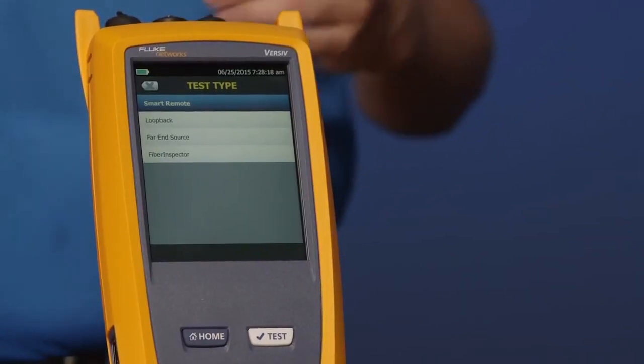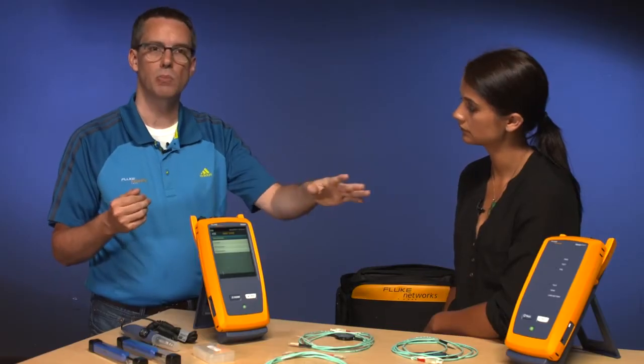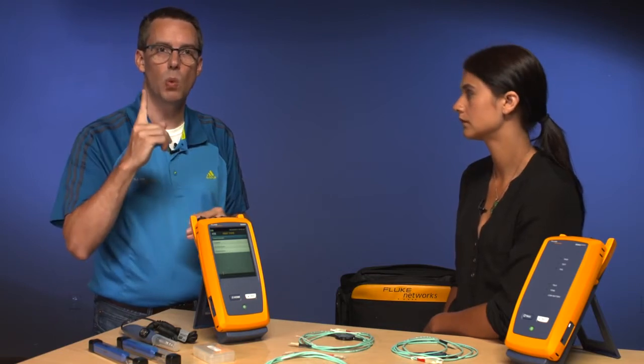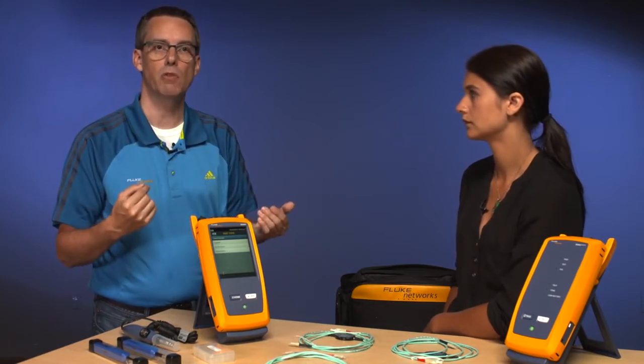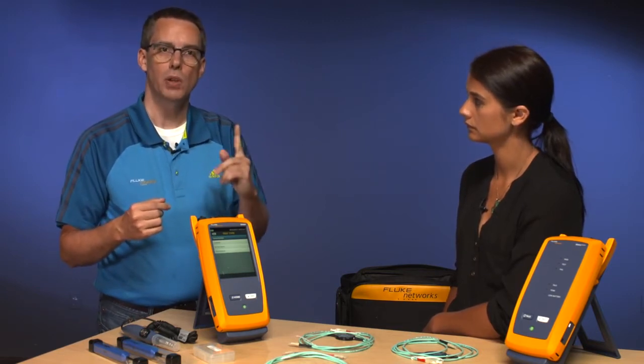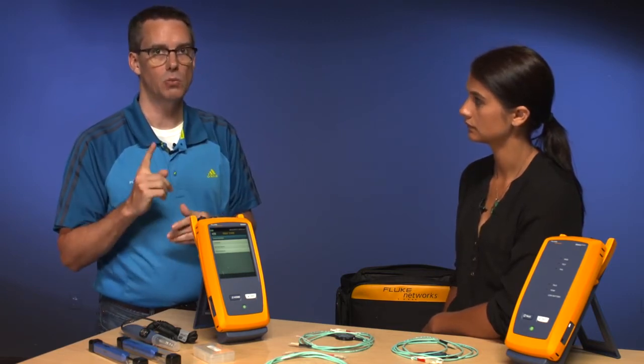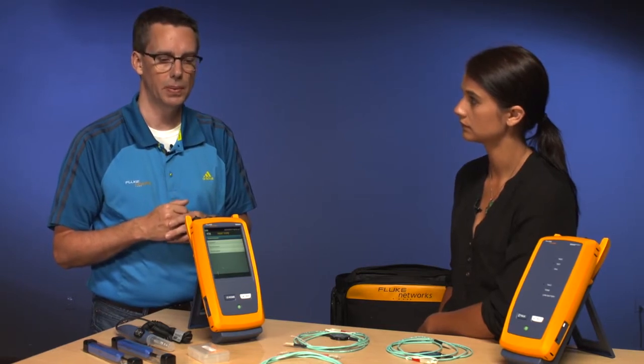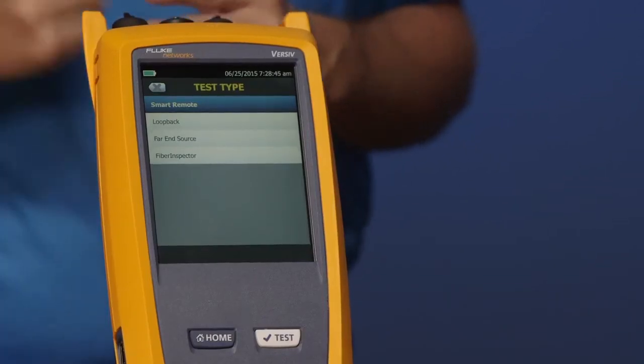There is also Far End Source, where we can just turn that into a simple source. So if we wanted to measure just one fiber, we can now measure one fiber. And unlike the previous DTX, we can measure both wavelengths on one fiber at the same time. That's really important when you're doing single mode. And then finally, there's Fiber Inspector.